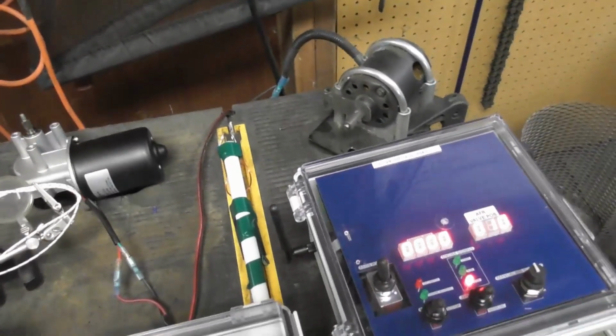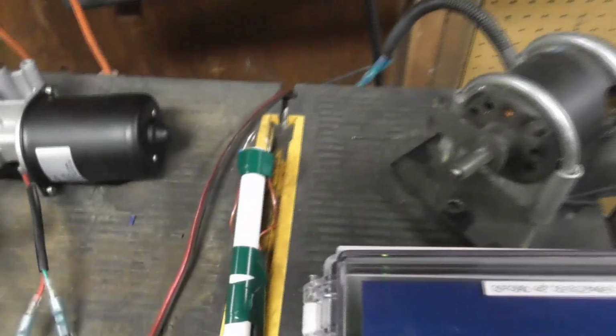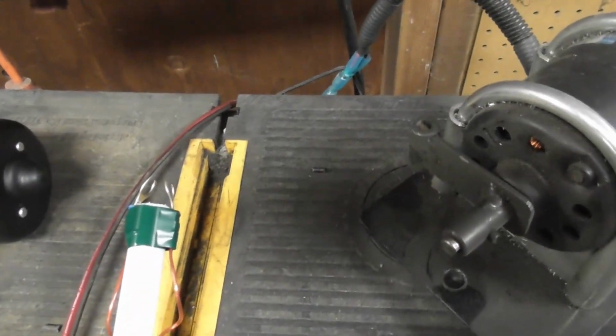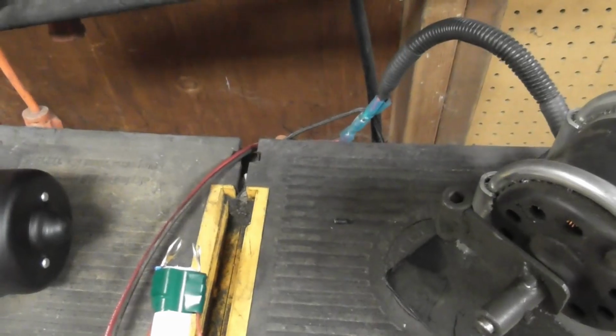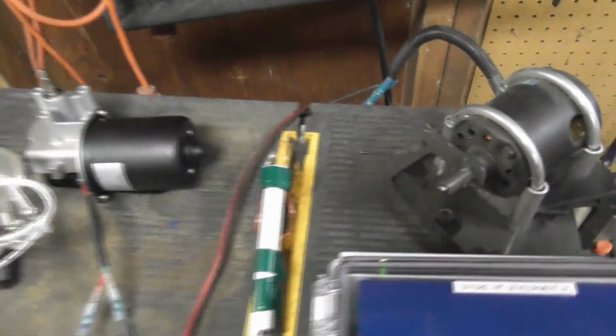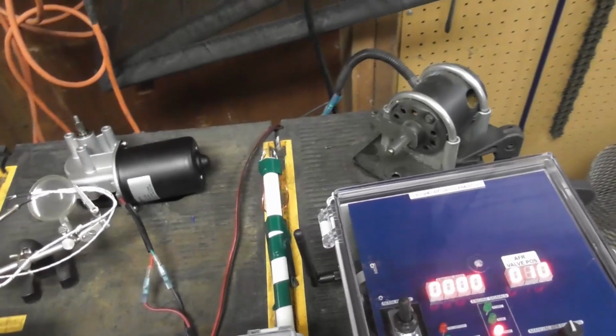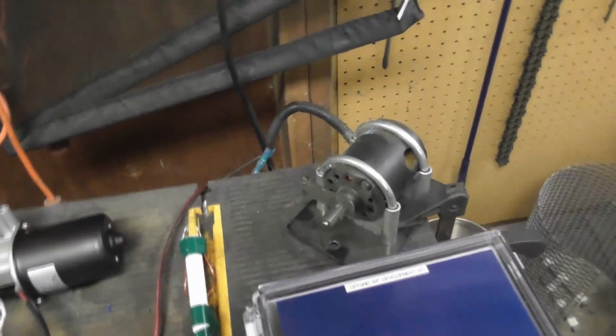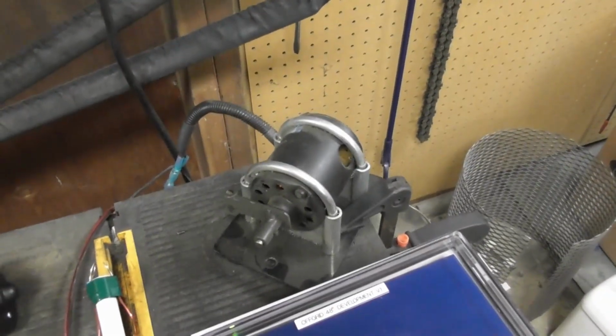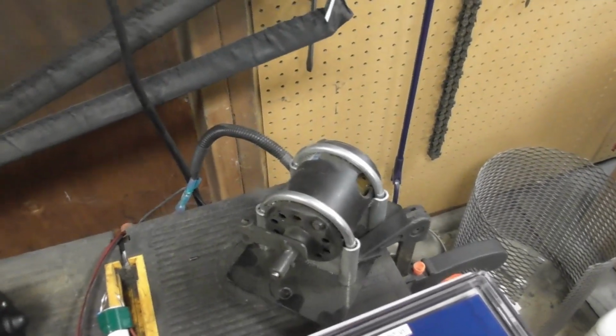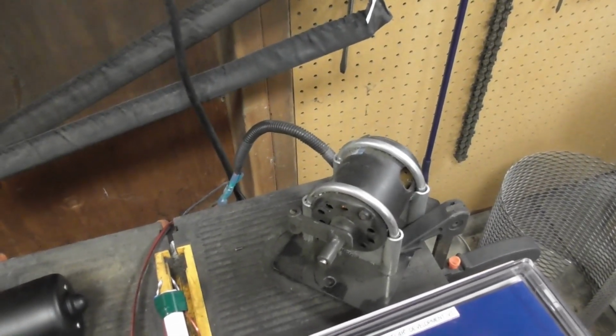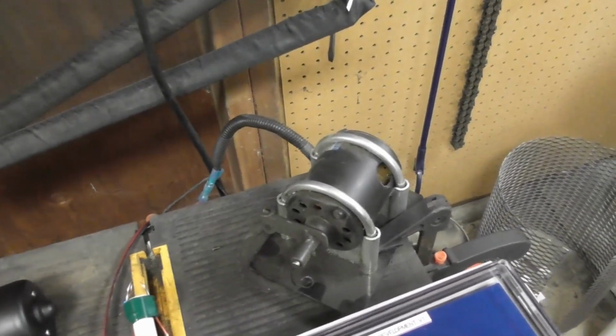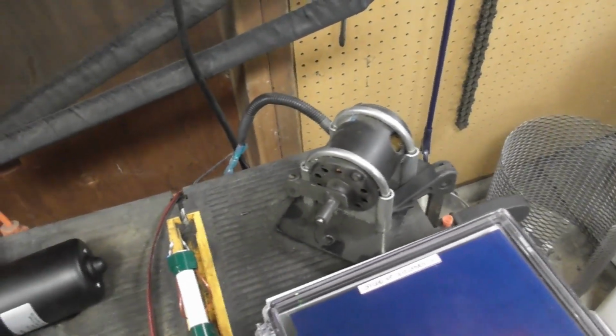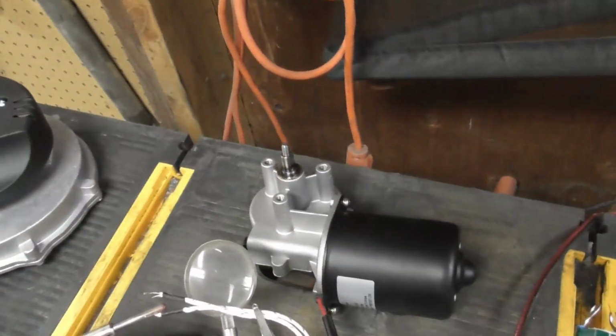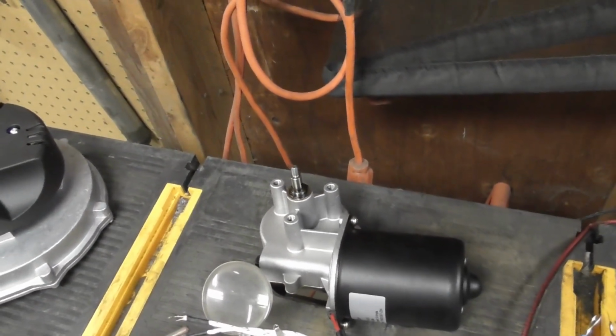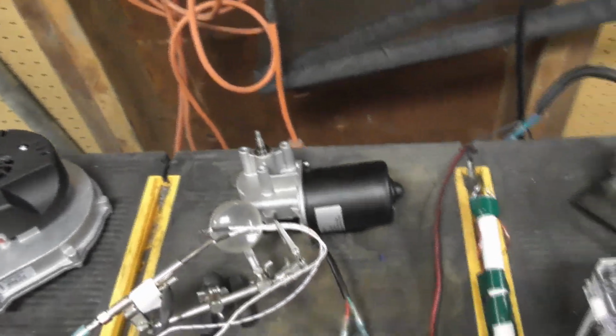Then we have the automatic flare start. So here you kind of see we've got this igniter here that will basically ignite the flare, and then we got a temperature sensor to detect when the flare is lit. Then we have another motor, if you wanted to have additional vibration to maybe the hopper or something like that to prevent bridging in your fuel. You can see here that motor's kicking on and off, stays on for 5 seconds and goes off for every 30.